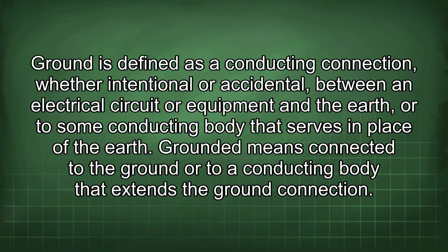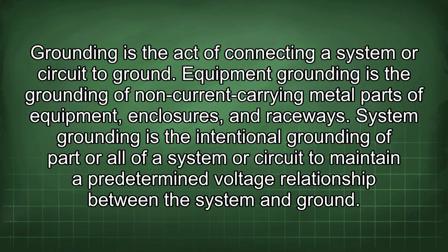Ground is defined as a conducting connection, whether intentional or accidental, between an electrical circuit or equipment and the earth, or to some conducting body that serves in place of the earth. Grounded means connected to the ground or to a conducting body that extends the ground connection. Grounding is the act of connecting a system or circuit to ground. Equipment grounding is the grounding of non-current carrying metal parts of equipment, enclosures, and raceways.